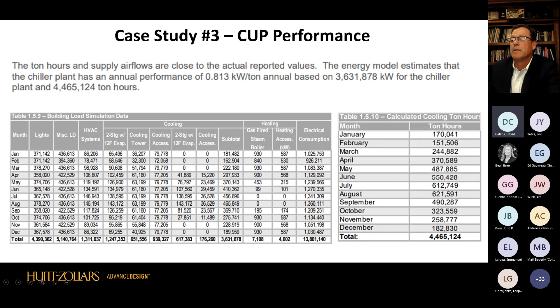At the end, we were able to give them a lot of information on the financials. We said, okay, you have a constant primary, constant secondary, that's where you're at 0.813. If you want your building to respond with a variable primary, variable secondary setup, it's going to cost you some money, but the paybacks could save them about $50,000, and overall they're going to save $165,000. But if they want to just get rid of all the secondary pumps, it's going to cost much more and take them 8 years.